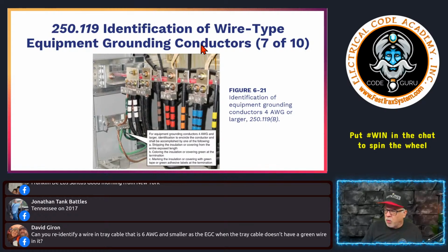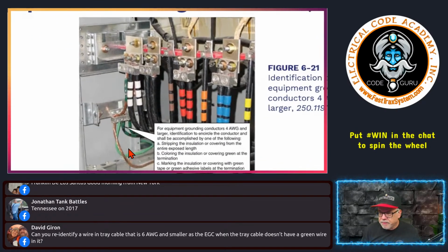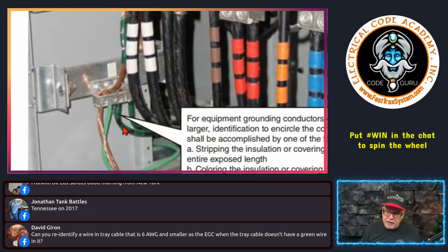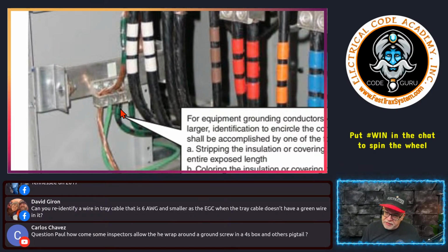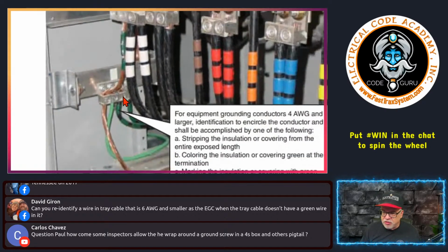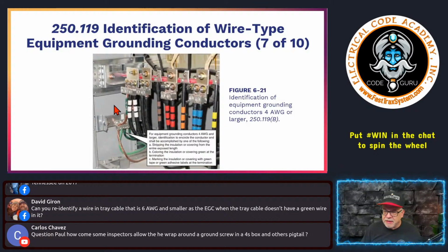All right, so wire type. Here's an example over here. I don't know if you can see it. I can zoom in on this. See, it's black, and they re-identified it here with the green. And they didn't have to do all this, right? I mean, it looks good, right? But this is perfectly acceptable right here. Now, this part, wrapping it on the bare, is kind of pointless, right? It makes no sense to me, because bare, we know what bare is, but hey, to each his own. I'm not going to be a hater. Haters ain't going to be hating, all right? But if you want to do that, that's fine. If you don't know what a bare is, then it is what it is, okay? So you're allowed to do it in 4 and larger, okay?